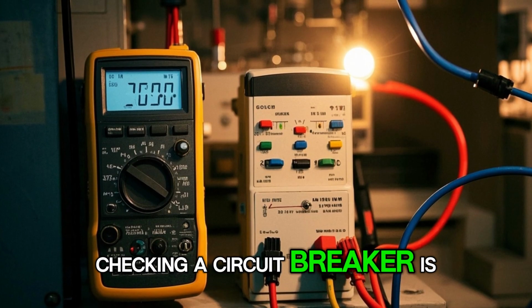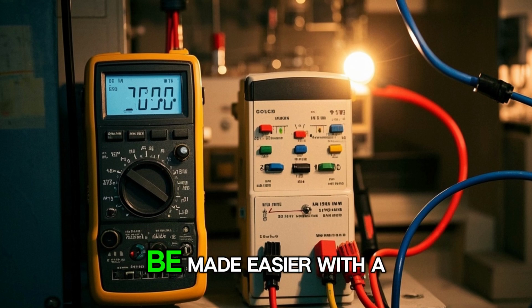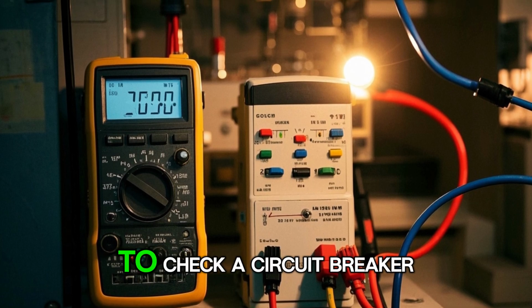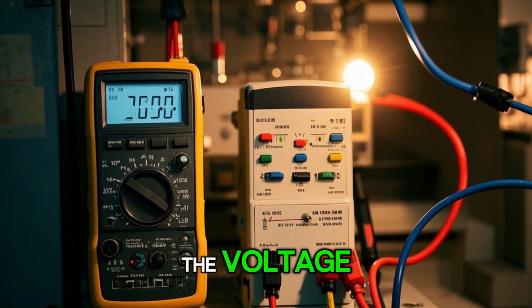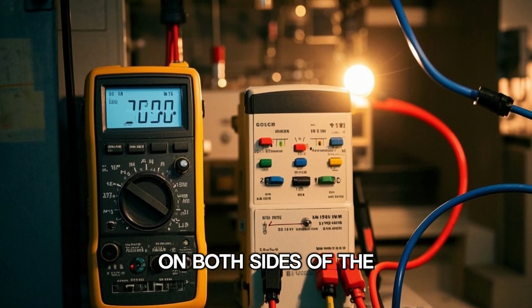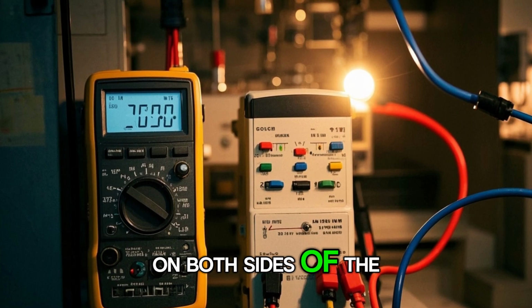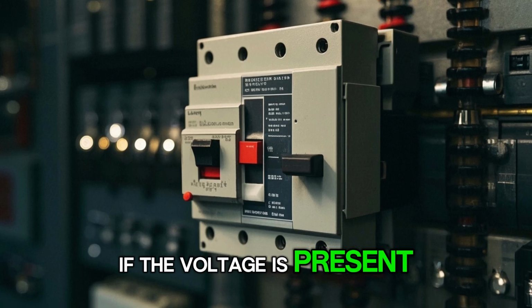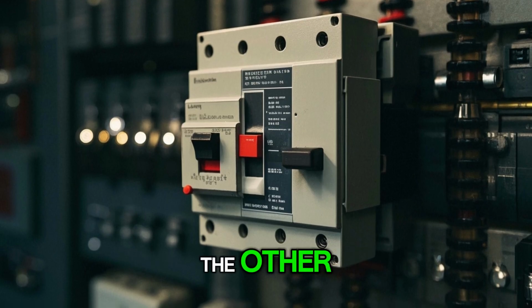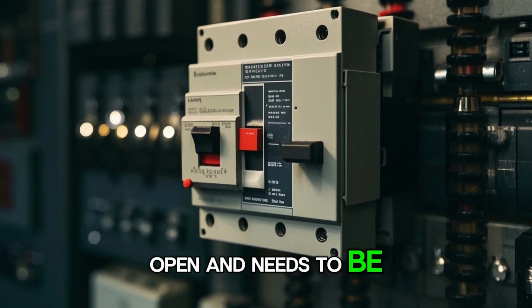Checking a circuit breaker is a simple task that can be made easier with a multimeter. To check it, measure the voltage on both sides of the circuit breaker. If voltage is present on one side but not the other, the circuit breaker is open and needs to be replaced.